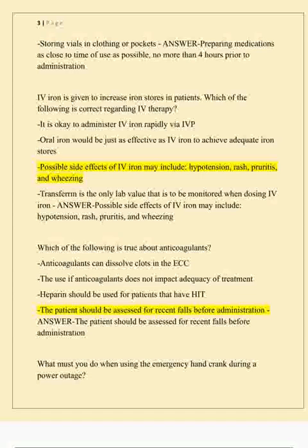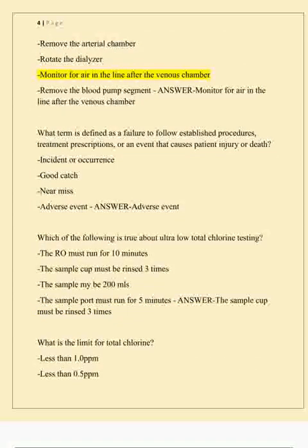What must you do when using the emergency hand crank during a power outage? Remove the arterial chamber. Rotate the dialyzer. Monitor for air in the line after the venous chamber. Remove the blood pump segment. Answer, monitor for air in the line after the venous chamber.